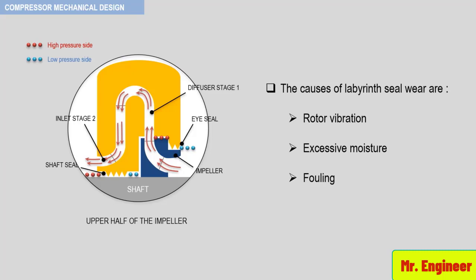A 10% drop in compressor head and efficiency with no evidence of fouling means that your stage seals are not performing their duties, and you need to check that as soon as you can.